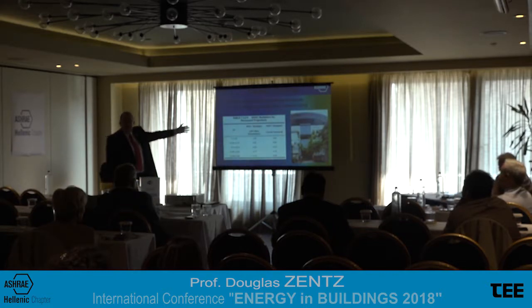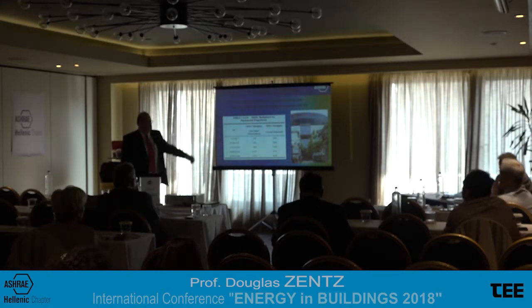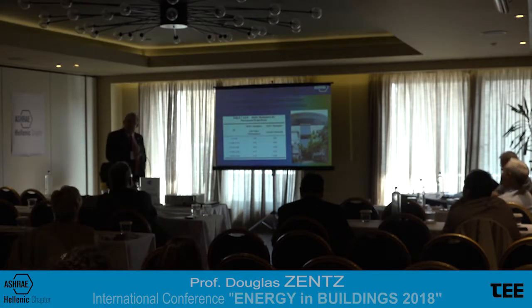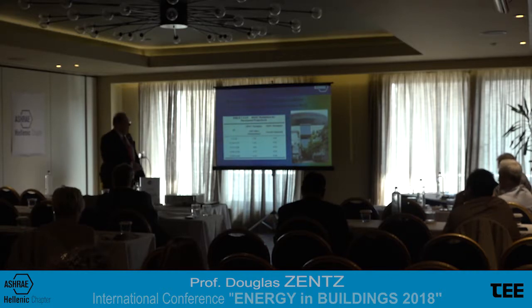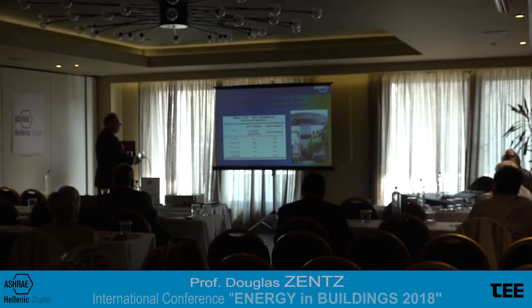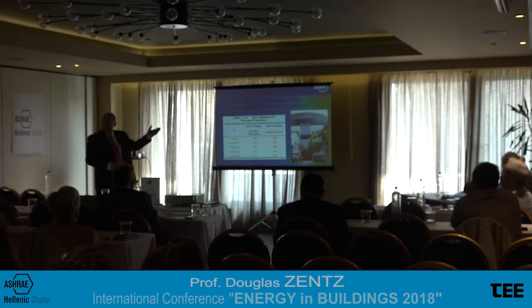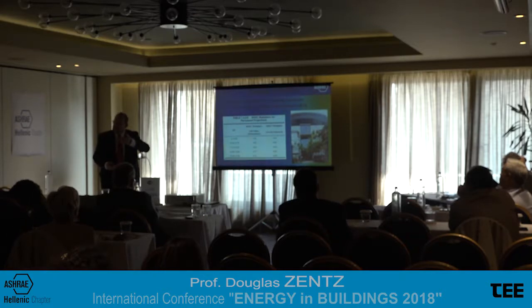Now, they do give you an out here on the size of the projections. Because if you got higher quality glass, or if you do the opposite, you put in more projection, you can use lower quality glass because you don't have as much direct solar on the glass. So they give you a table here that basically says, if your overhang is bigger, you can use lower performance solar heat gain factor glass because it's going to be shaded most of the time, which is a nice credit.